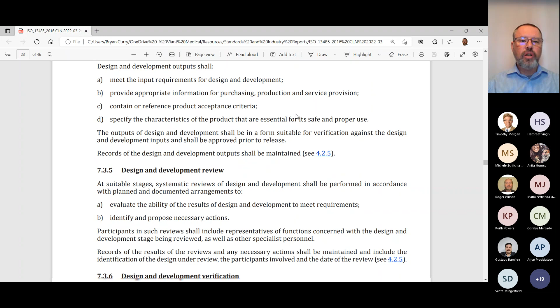this is what I was talking about, where you have those stage gate review meetings that have very specific requirements. They happen at the different phases of the design process. So the planning process, inputs, outputs, verification, and validation. These reviews have to have a very specific set of attendees. You have to have the appropriate personnel. Frequently, it's all the functional areas that approve a lot of the design documentation. Your intent in these meetings is to show that you have satisfied all of the design requirements up through that stage before moving on to the next stage. In reality, many design stages happen in parallel.